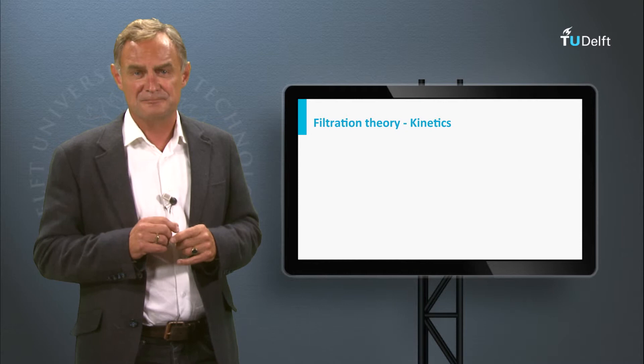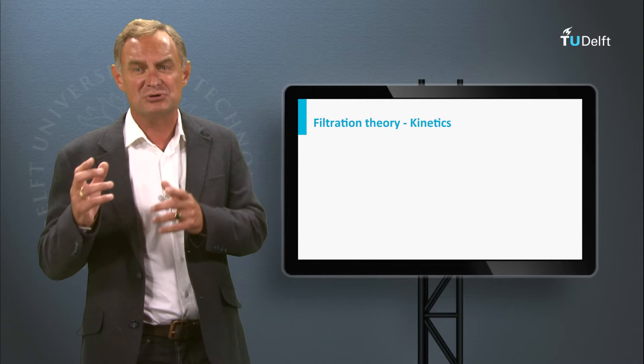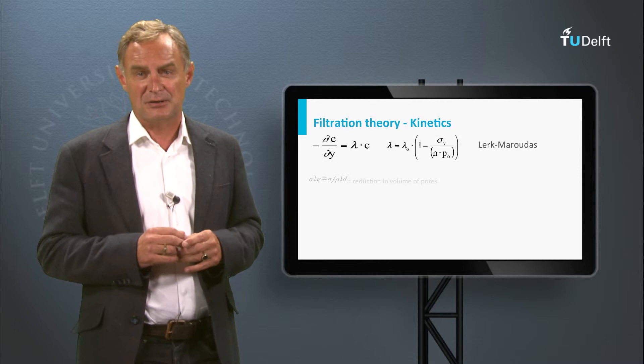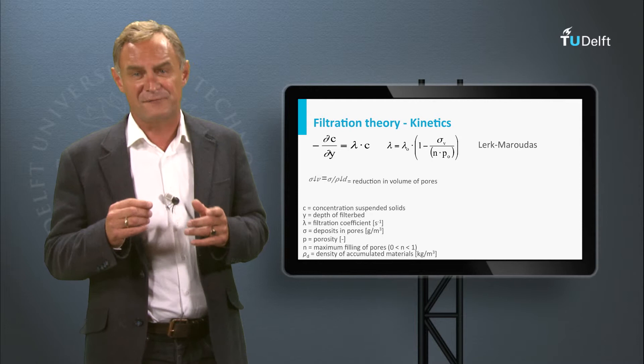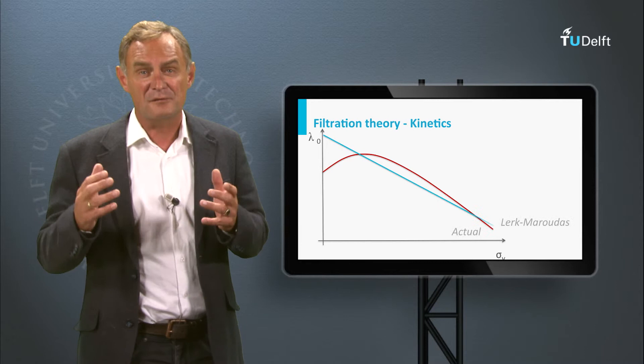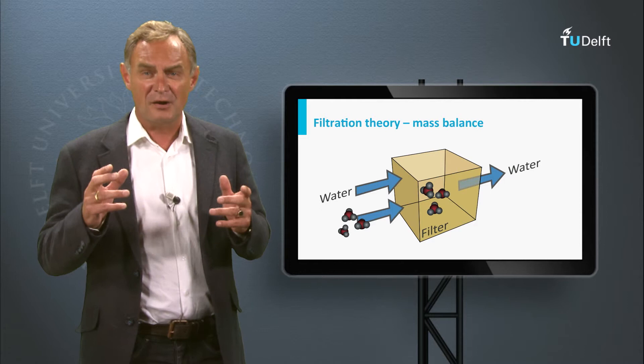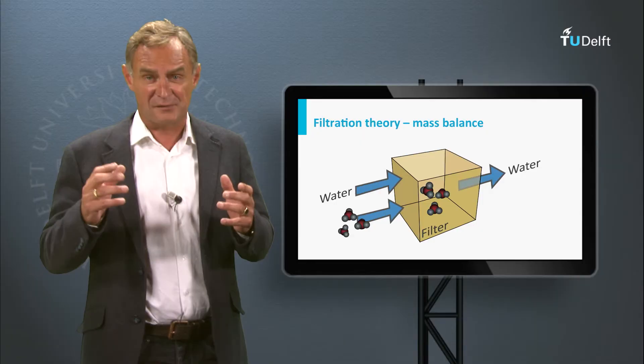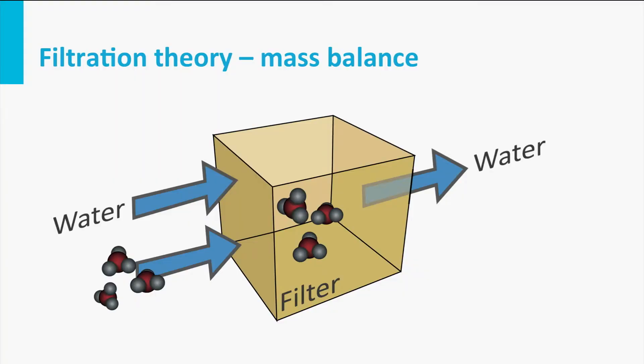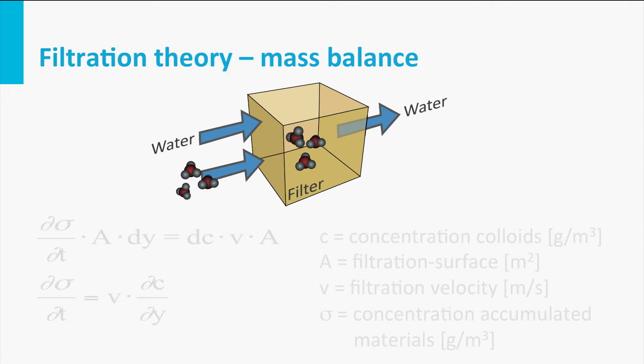The change in water quality over the height of the filter bed is determined by the so-called filter coefficient lambda and the influent water quality. When the filter bed is clean, the filter coefficient is relatively large, but it gradually diminishes because of the accumulation of solids in the bed. The accumulation of solids in the bed is the consequence of the law of conservation of mass: it equals the removal of these solids from the water phase over time.